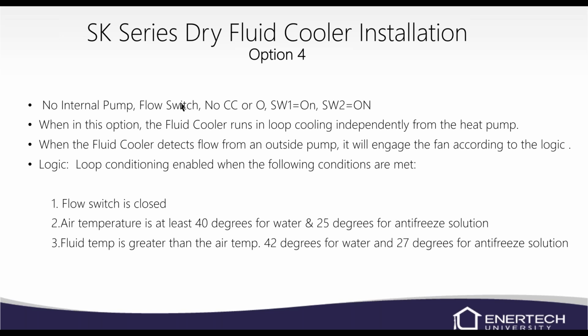So it works somewhat independent of the heat pump. It does rely on the heat pump's flow from the external pumping, but it'll look at water and air temperatures, and then decide whether it's going to run or not, as long as the flow switch is closed.